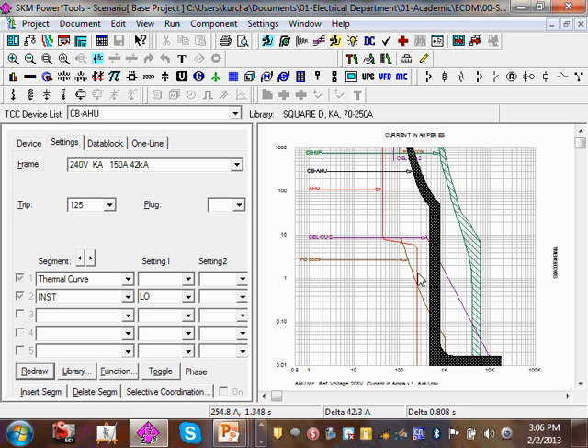Anyway, so that's what we call, guys, the coordination. You need to coordinate between the main and the feeders, as well as the equipment that's protected by the feeders. And that's as easy as, I don't know if you can see the instantaneous here. You can set it at 2. Can you guys see how it moves? You can set it at 3.